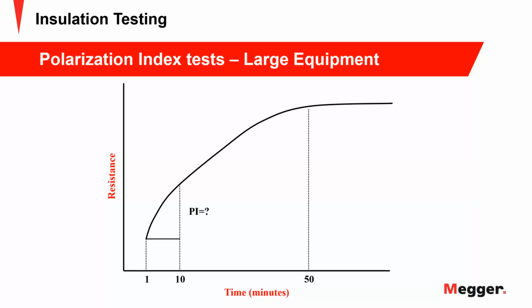But you don't necessarily need to be all the way up on that high end, and you certainly don't have the time in your work schedule to take an hour. So instead, the PI, 10 minutes, it's looking at how the readings are changing, and it's looking at why the readings are changing. And so you can make a decision based on that and not spend so much time testing. Next.